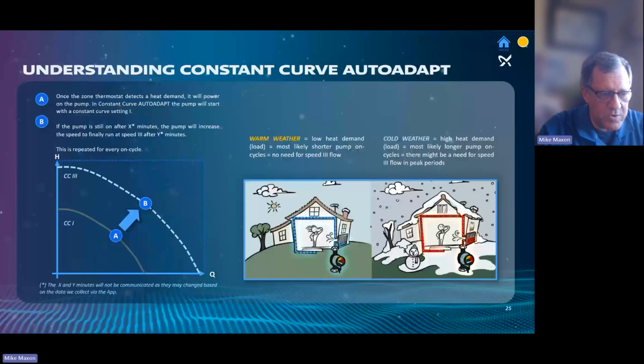Constant curve auto adapt. When I heard this one, constant curve, I wondered, what are we adapting if we're constant curve? The word constant is the word for not changing. But we all know that many pumps are put in speed 3, also known as never callback, so that on that coldest day of the year, that zone, that system will get the max amount of flow. On the moderate day, it's still going to get the maximum amount of flow, but it's going to work. So what we've done is we made this constant curve auto adapt where the pump will start every time it starts in speed 1.